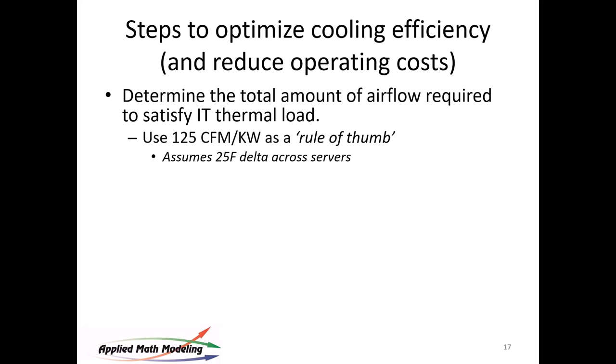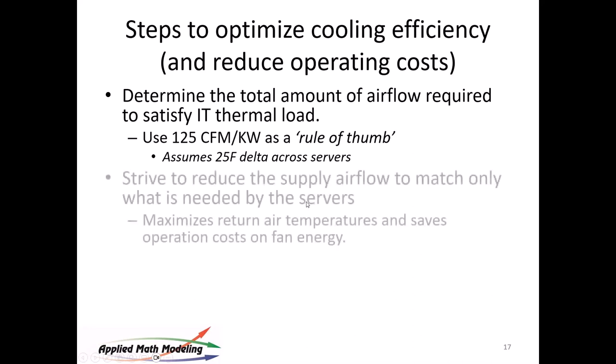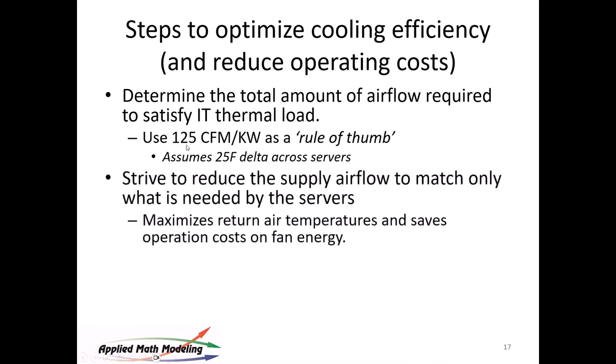Right, and the chips are getting more tolerant, and the heat exchangers on the chips themselves are getting better. So 125 is actually now a fairly conservative number, as Magnus just pointed out. They're often going to 100 on this. So if the math is easier at 100, just think of 100. But it's a fairly good rule of thumb.